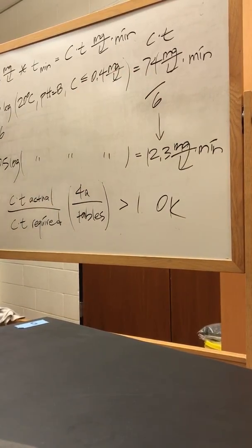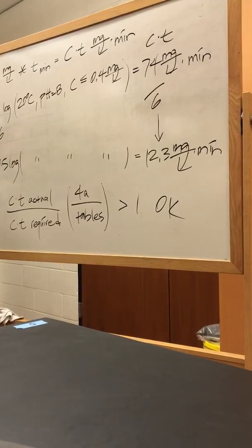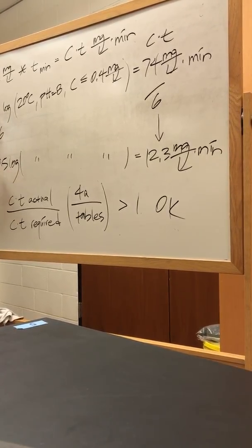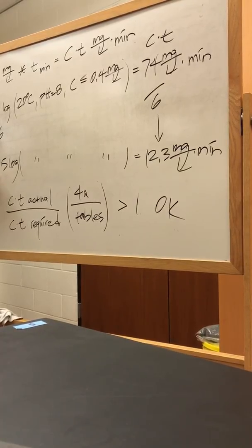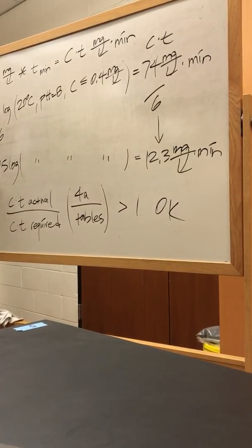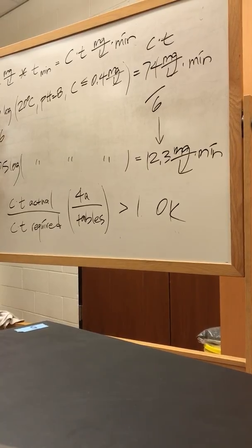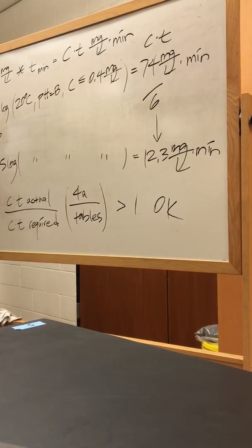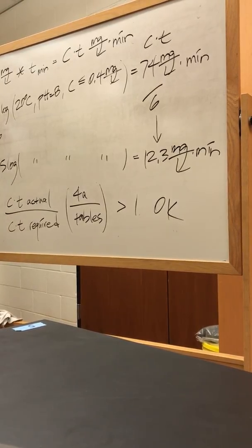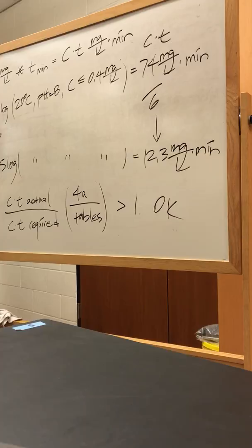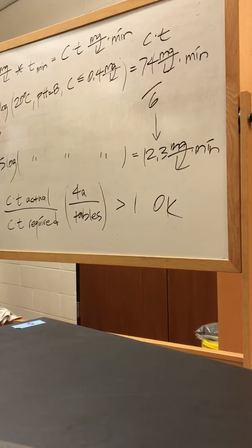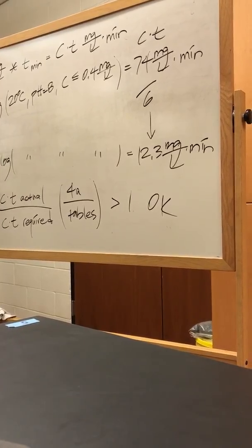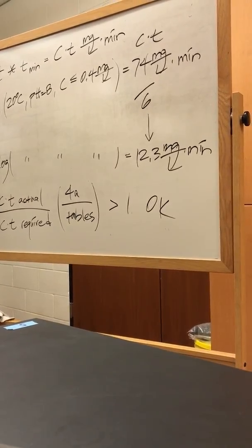Then, again, the problem asks you, what if you need 0.5 log removal? And remember, we can get credit for filtration, depending on the filtration type. So if you have a conventional system with coagulation, flocculation, filtration, you can get 2.5 credits, and that's on that table I showed in class, 2.5 credits for Giardia removal.